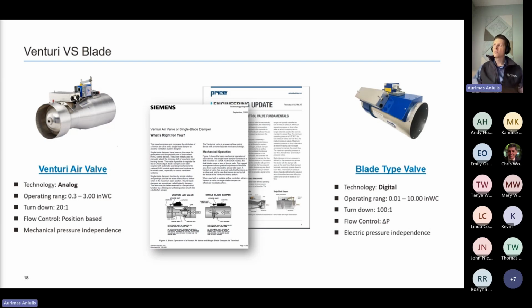So now, if you ask me, in the next 10 years you're going to see more and more blade style valve specs come on the market because of energy efficiency. The lower operating pressure range, or the wider operating pressure range, for the blade style air valves becomes a very appealing proposition when designing a lower pressure system out the gate, right? With the Venturis, the floor is 0.3, and you can't operate the valve lower than that.